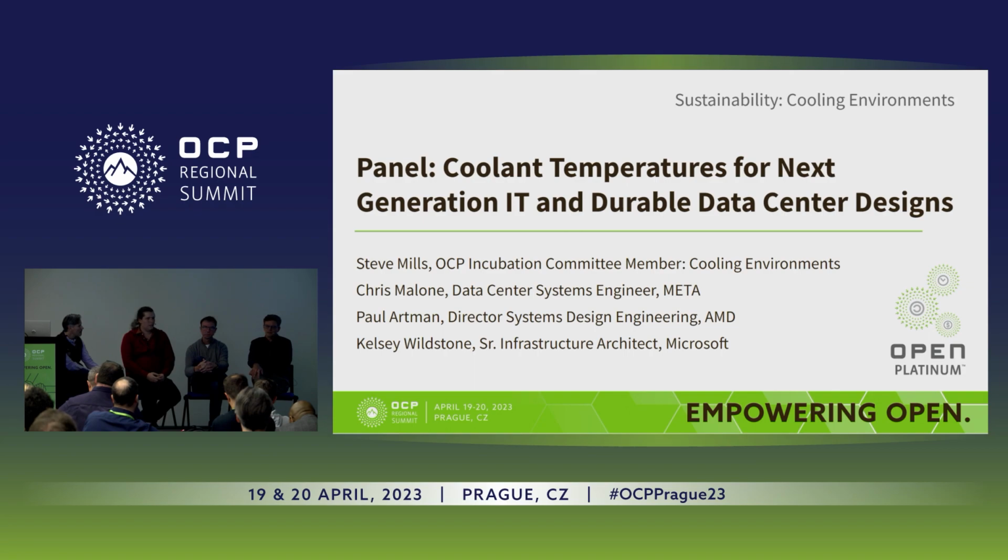Yeah, I agree with what Kelsey said. There is a move in the industry towards using less or no water at the data center side. That typically does mean more energy consumption, so it's a balancing act. In picking these interfaces, we have to think about how much durability and flexibility we build into this new multi-billion-dollar data center without going overboard. Every degree that you lower that design temperature means not only more cooling, but more power that goes along with powering that infrastructure. So that's the thinking that goes into this kind of spec.